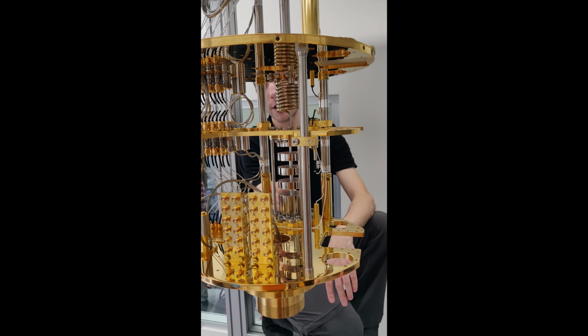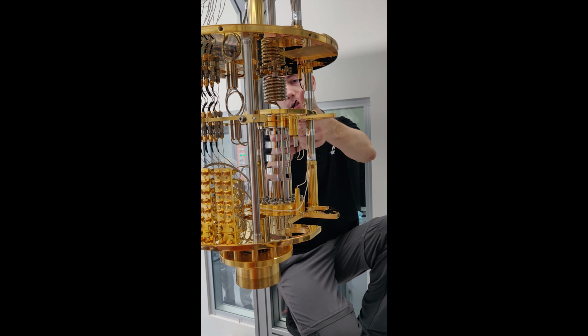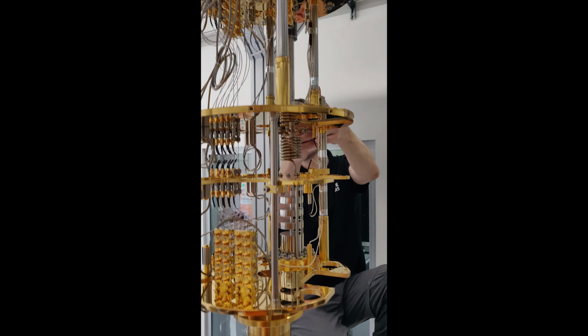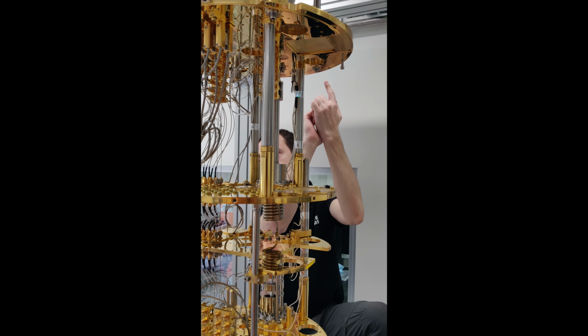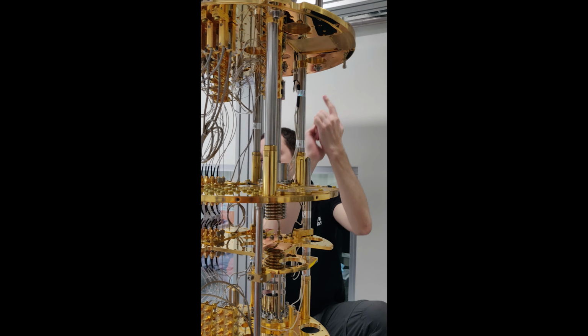So the idea is that this whole dilute phase fills up to the still. At the still, we pump helium-3 out of it, utilizing another fancy property of helium-3: its vapor pressure is much higher than helium-4's vapor pressure at a given temperature - a couple of orders of magnitude more. So mostly all the vapor here consists of helium-3, and we pump it out through this huge line to have as low resistance as possible.